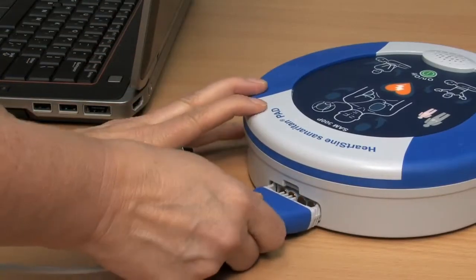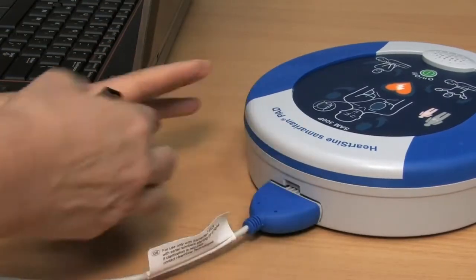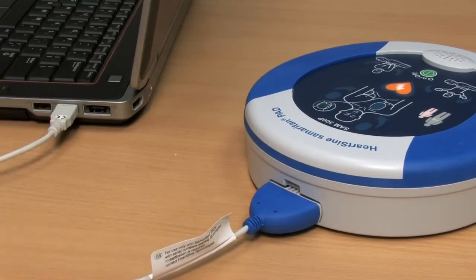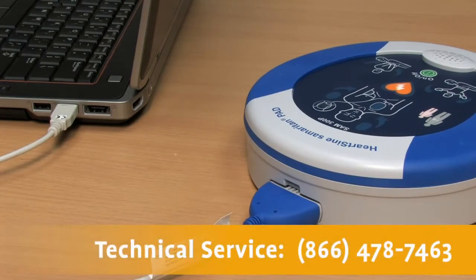Use the supplied data cable to download the event data for a physician who may want the information from the device to formulate treatment decisions. The data cable comes with the PAD at no additional charge and is available from your authorized HeartSine channel partner. After downloading the event data, please erase the data from memory. If you need assistance, contact HeartSine Technical Service at 866-478-7463.